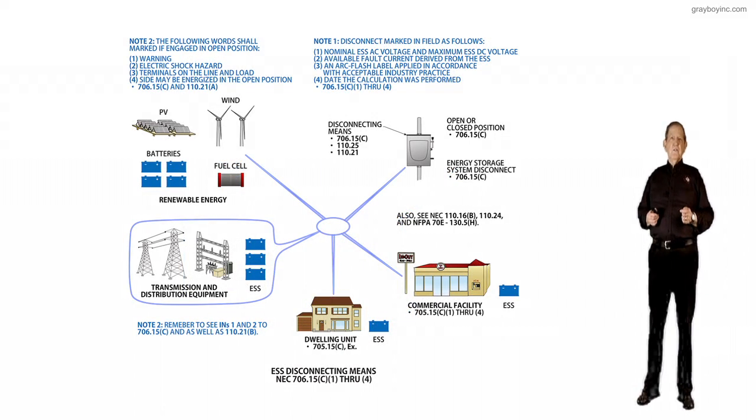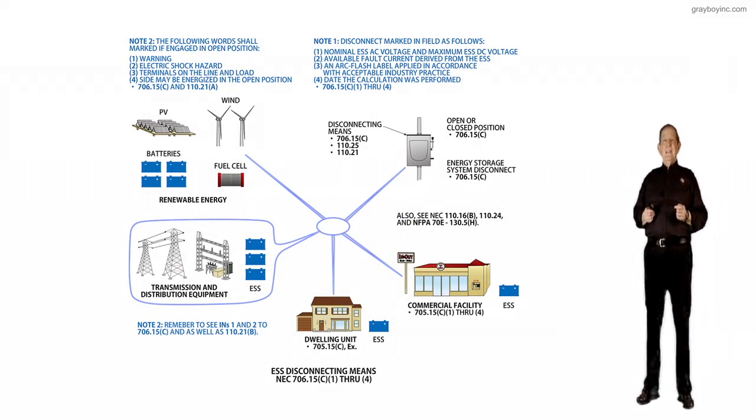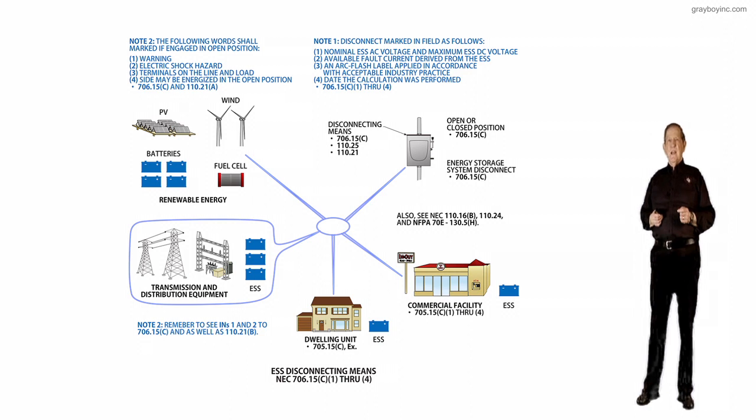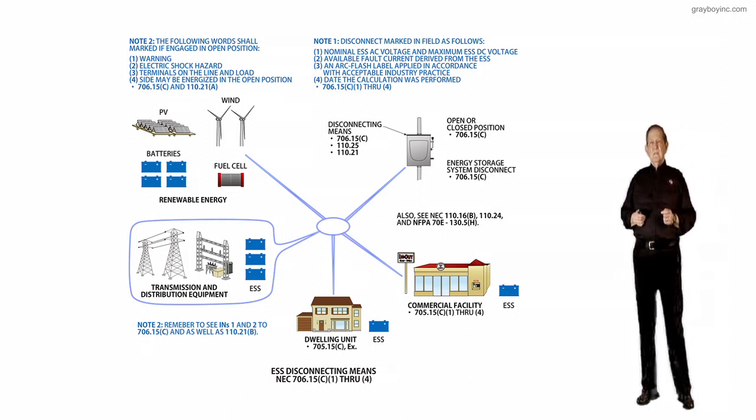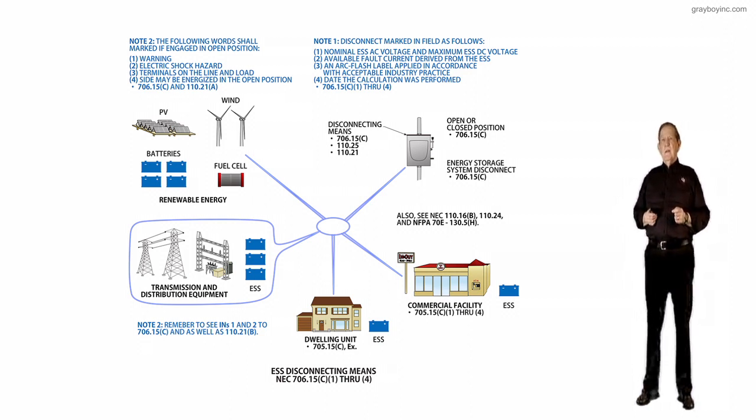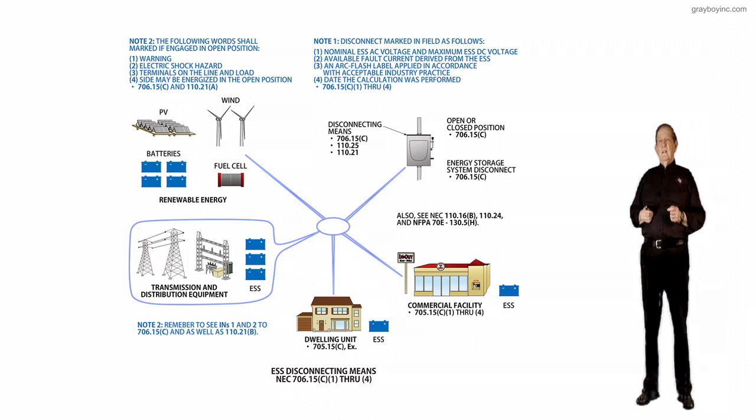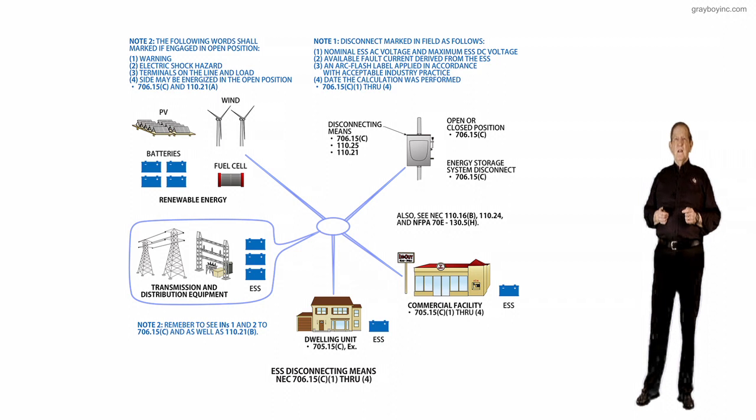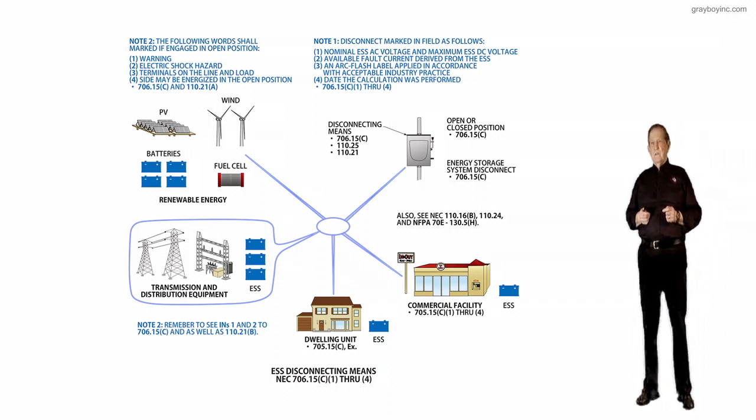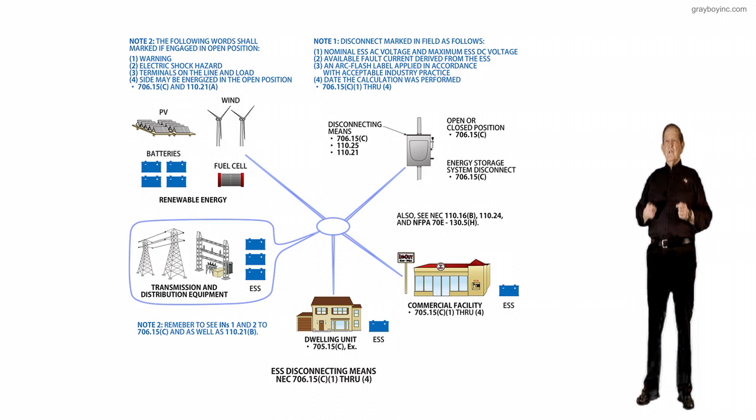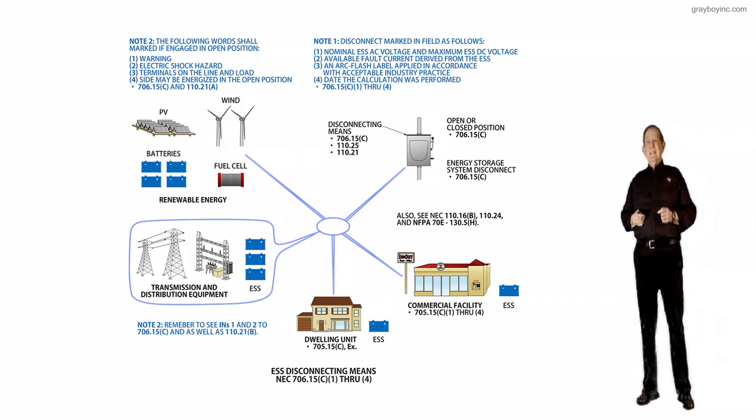This illustration deals with the ESS disconnecting means in accordance with 706.15A1 through A3. The purpose of this change: a revision was accepted and has been added to make it very clear that a disconnect shall be provided for all ungrounded conductors derived from an energy storage system, ESS.